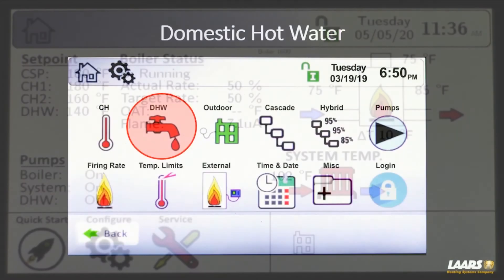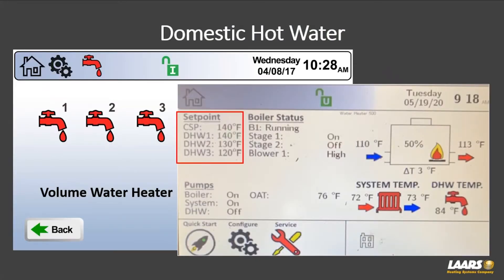For domestic hot water on a volume water heater, you'll see the home screen shows three different DHW set points: DHW1, DHW2, and DHW3. On a volume water heater you don't have CH — you have DHW. DHW1 and DHW2 work just like central heat: they operate on the outlet sensor of the boiler. So you could program DHW1 and DHW2 for 140 and 130 degrees on the outlet temperature. You would also use a mechanical aquastat on a holding or storage tank.